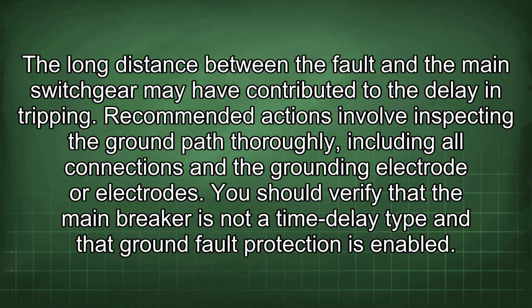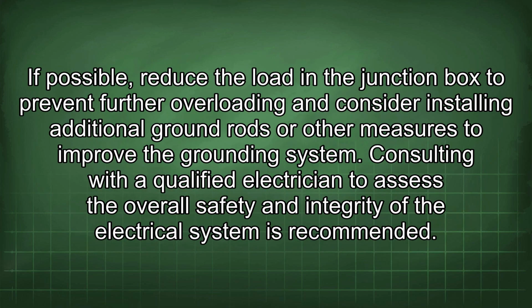Recommended actions involve inspecting the ground path thoroughly, including all connections and the grounding electrode or electrodes. You should verify that the main breaker is not a time delay type and that ground fault protection is enabled. If possible, reduce the load in the junction box to prevent further overloading and consider installing additional ground rods or other measures to improve the grounding system. Consulting with a qualified electrician to assess the overall safety and integrity of the electrical system is recommended.